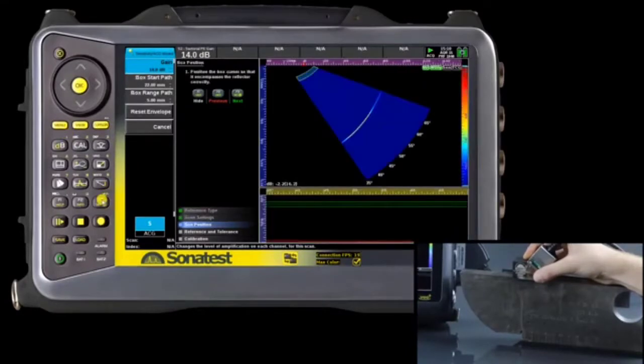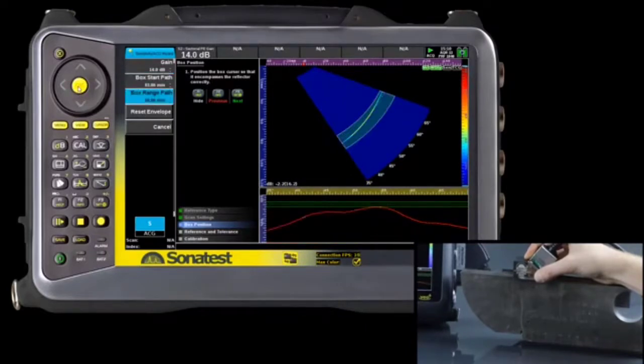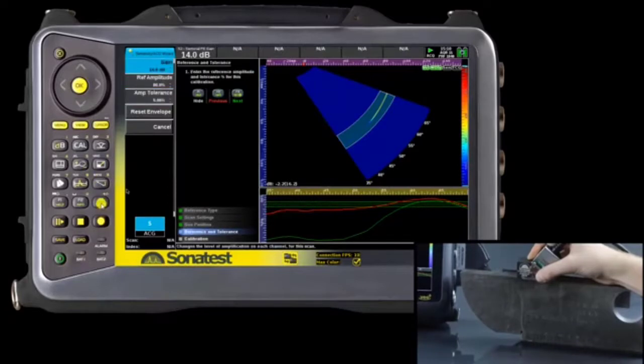The next step is to set the extracting box dimensions, making sure that all the signal is within the box. Once the radius has been swept completely, we can easily see that some angles have higher responses than others. The reference is set at 80% and the tolerance at 5%, which is good because the signal response is already close to the value.